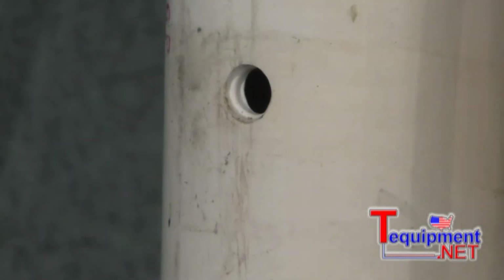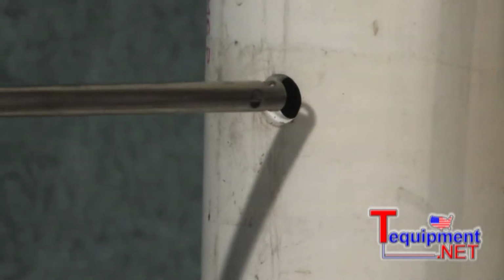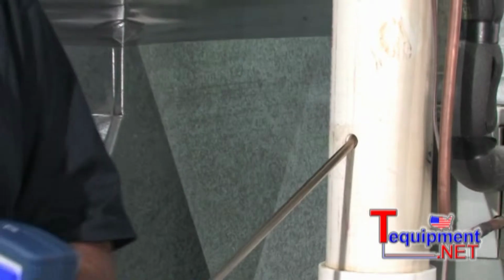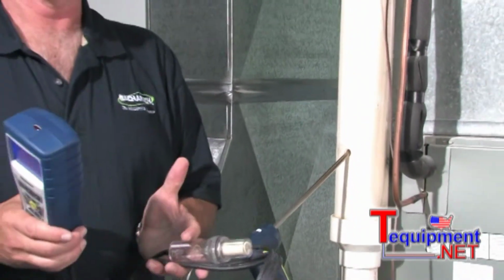Okay, on this particular piece of equipment, we drill a hole in the PVC pipe. We're going to insert the probe into that hole. Check with the manufacturer of the equipment that you're installing and servicing, whether it's an oil-fired piece of equipment, gas-fired piece of equipment, a condensing unit, an old atmospheric piece of equipment, or an 80%er. Check with the manufacturer of that piece of equipment to determine what readings you should read in the display of this instrument. A few other things to keep in mind.